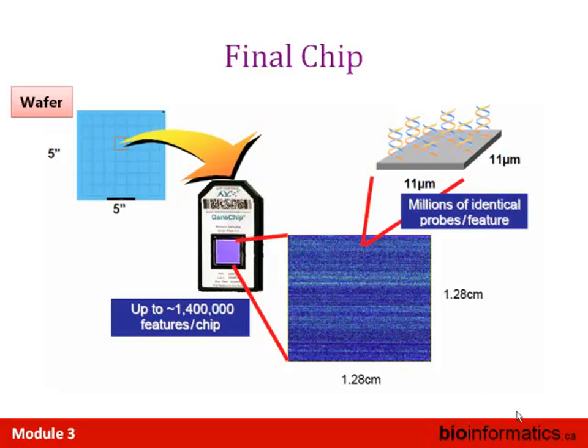Let's look at the structure of an Affymetrix array — this is an older one, about 8 or 10 years old. The initial wafer is 5 inches by 5 inches, and from that a tiny piece is taken for each microarray — roughly 100 individual arrays from a 10-by-10 grid. Masks are used to shine light repeatedly, making 100 identical arrays. Each spot is 11 microns by 11 microns.